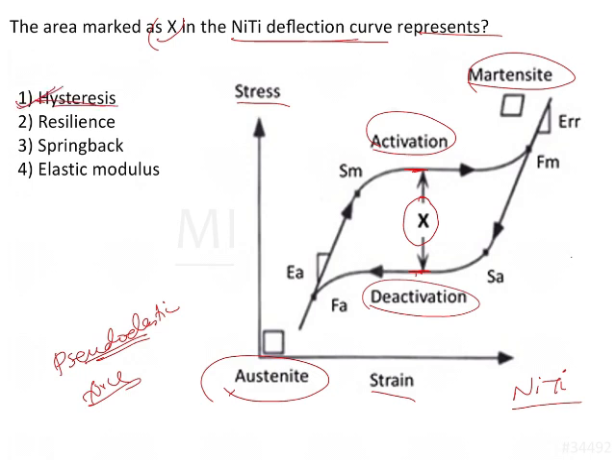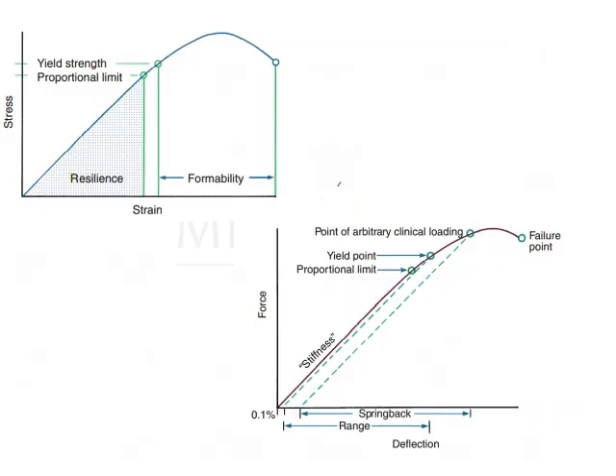This is a very characteristic type of graph seen only with nitinol wire because it expresses pseudo-elasticity. Had it been any other material such as stainless steel, the graph would look something like a straight line, after which on excessive force, the material will get deformed.